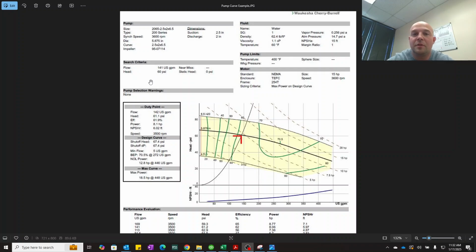The thing to remember for centrifugal pumps is that they're really good at medium to high volumes at relatively low pressures. So what does that mean? Medium and high are sort of relative terms. In our world, it typically means between 50 and maybe 250 gallons per minute for flow. And then for pressure, generally we see it anywhere between 10 and maybe 60 or 75 psi.